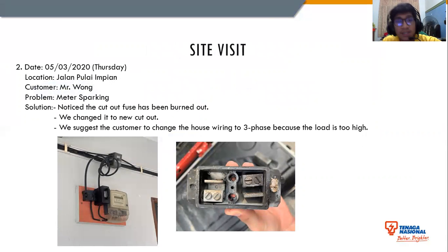Okay, the second site visit is at Jalan Pulai Impian. The customer is Mr. Wong. The problem is we noticed the meter is sparking. We noticed the cutout fuse has been burnt out, so we changed it to a new cutout. We also suggested the customer change the house wiring to 3-phase because the customer is using single phase. The reason the cutout burnt out is because the load is very high.